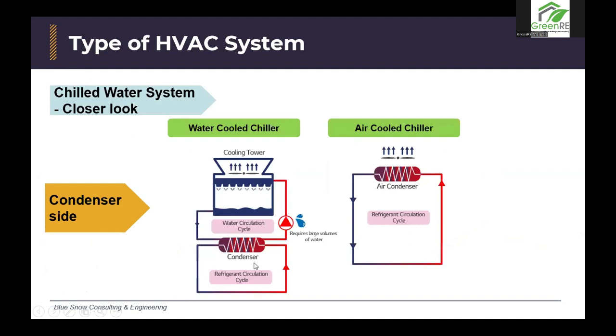Okay, the next one, I will tell you the main difference between the water cooled chiller and the air cooled chiller. First, we need to determine where the condenser is. Okay, this is the condenser for the water cooled chiller, which is connected to the open loop water, which is connected to the cooling tower. Different from that, the air cooled condenser is straight away exposed to the air, and with the help of the fan, it will cool down the coil and the refrigerant inside the condenser.